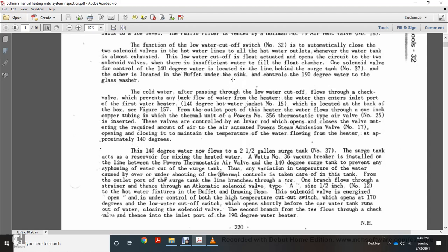140-degree water flows to the two-and-a-half gallon surge tank number 37. The surge tank acts as a reservoir for mixing heated water. A Watts number 36 vacuum breaker is installed in the line between the Powers thermostatic air valve and the 140-degree surge tank to prevent any cycling water out of the surge tank and variations in temperature from causing over- or under-control. From the outlet port of the surge tank, the line branches through a tee: one branch flows through the strainer and an Atkomatic solenoid valve to the hot water fixtures above the drawing room. The solenoid valve is energized open, controlled by the high-temperature cutout switch and the low water cutoff switch, which opens before the car water tank runs out.